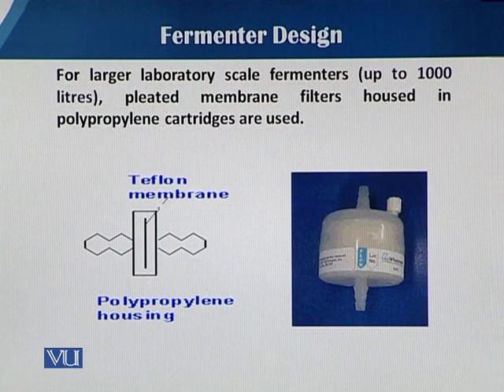You can see in this slide the teflon-type filter and how it is designed. It has a teflon membrane inside, and this whole membrane is packed within a polypropylene housing, because polypropylene can withstand its shape and quality under sterilization — we have to autoclave it before use. This type is mostly used up to 1000 liters.